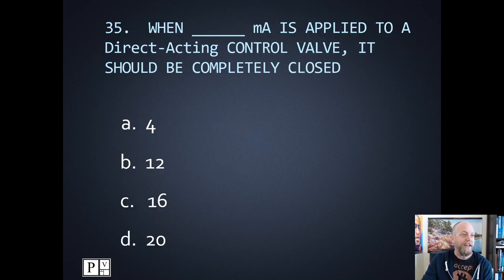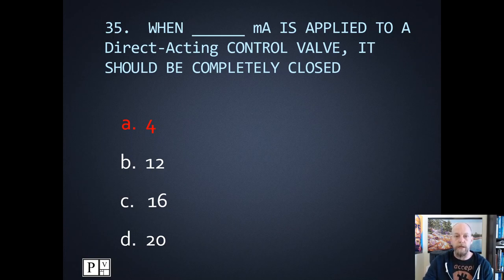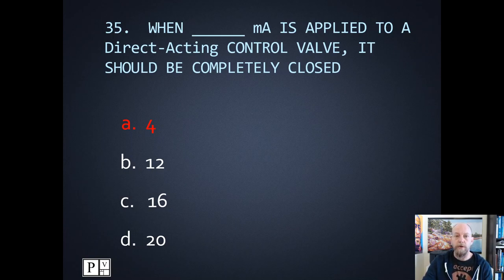Number thirty-five: when how many milliamps is applied to the direct acting control valve should it be completely closed? This corresponds to the current to pressure transducer. 4 milliamps is the value that corresponds to 3 psi — the lowest pressure. Lowest current, lowest pressure, the valve is most likely closed. If we had 20 milliamps, then we'd have 15 psi applied to the valve and it would be open. Being a direct acting control valve.